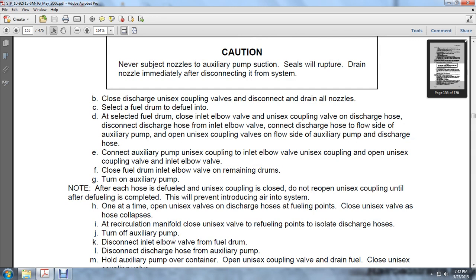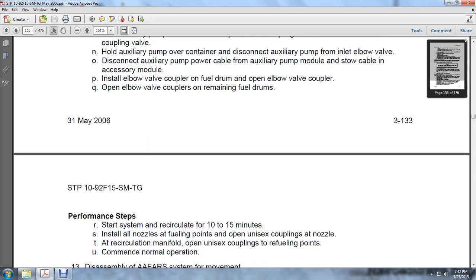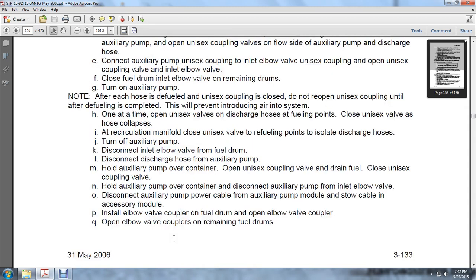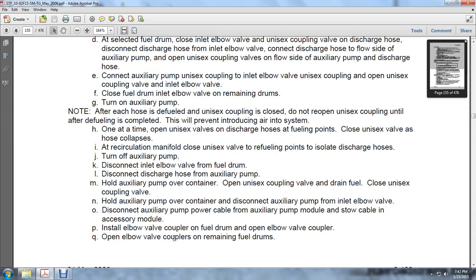After each hose is defueled, the unisex coupling is closed. After each coupling is closed, do not reopen the unisex coupling until the defueling is completed. This will prevent introducing air into the system. Open the uniset valves one at a time, open the discharge hoses at the fueling points. Close the unisex valve as hose collapses.